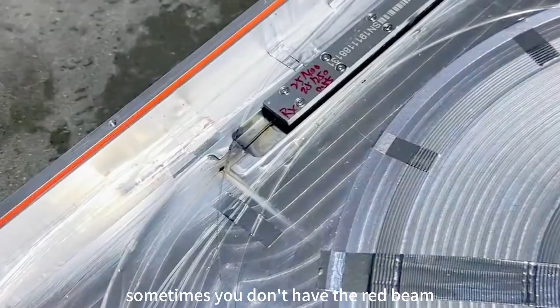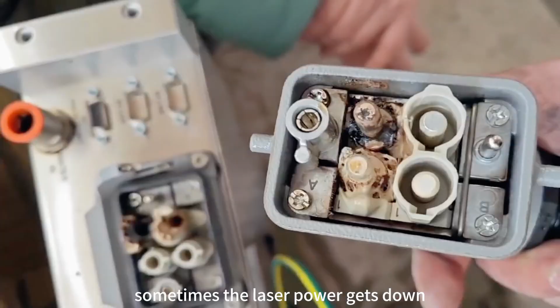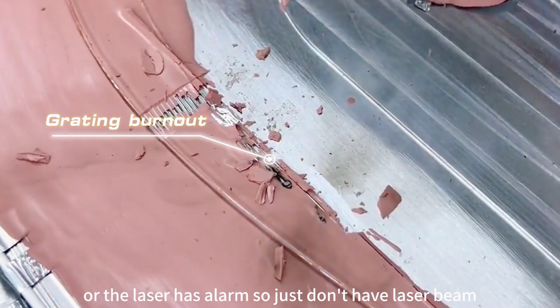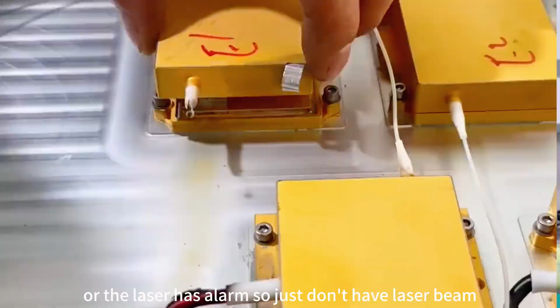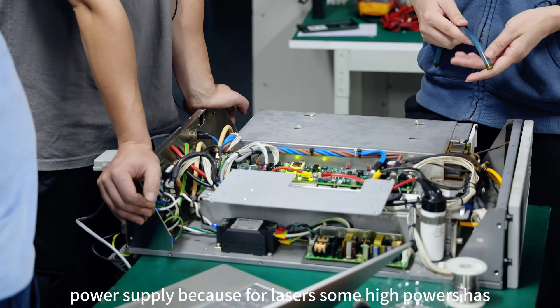For pulse, sometimes you don't have the red beam, sometimes the laser power goes down, or the laser has an alarm and there is no laser beam. If this happens, your laser has problems. First, you need to check the power supply, because for lasers, some high powers have 240 volts, but for these small powers, you have a 48 volt supply. You just need to be sure that all the plugs are in good condition.